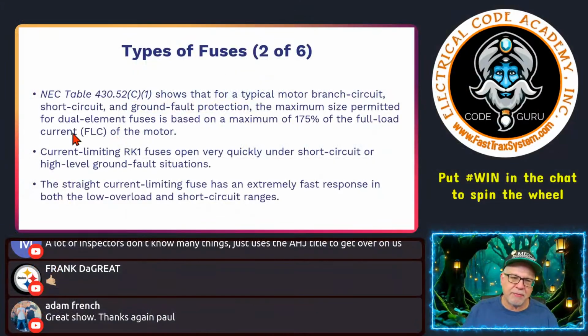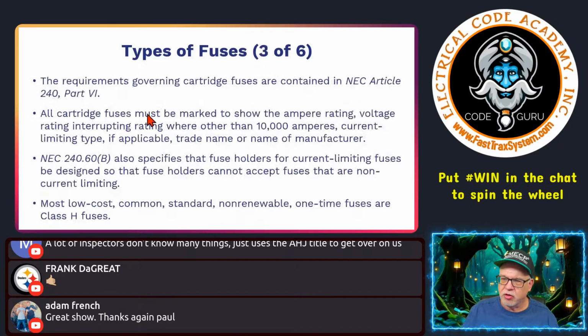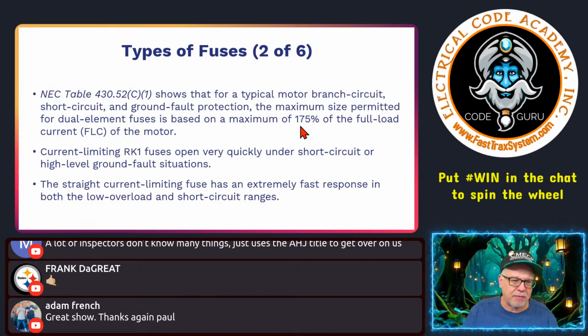So there you go. So the time delay, the dual element application is going to have a maximum of 175%. Notice that's a maximum. You can't exceed that. Now, you do have some allowances underneath it, some notes, where something doesn't correspond to the values given, or the rating is non-adjustable, and that type of thing.